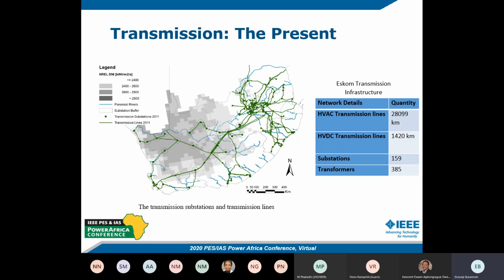Its HVAC transmission system consists of a total of slightly above 28,000 kilometers, operated at standard voltages of 765 kV, 400 kV, 275 kV, and several other voltages as listed in the legend. The majority of these lines are 400 kV, and there are about 325,000 kilometers of distribution lines. A step-up transformer boosts the power as it leaves the power station at a voltage as high as 765 kV, and it is stepped down for customer distribution at substations near the load centers.